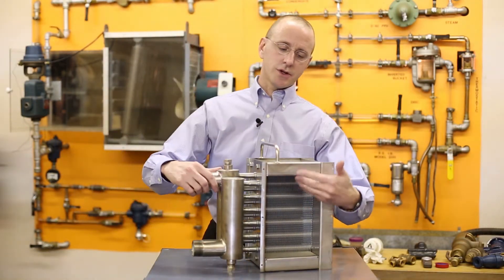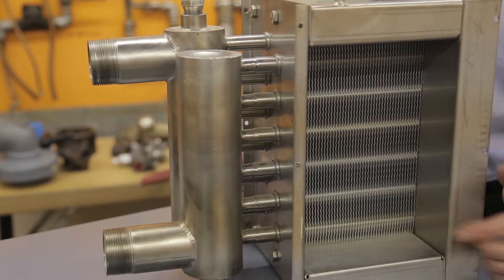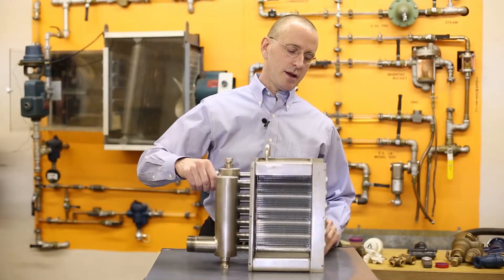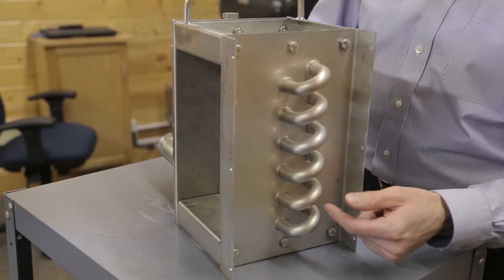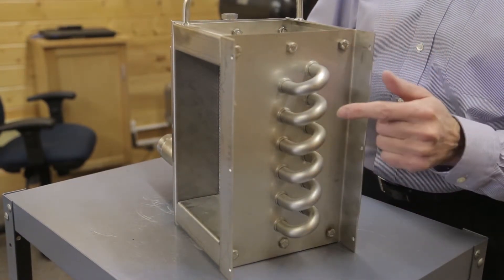The tubes are expanded into the fin collar using mechanical expansion. And then on the back side there's either brazed u-bends or the u-bends are bent out of the tubing itself.